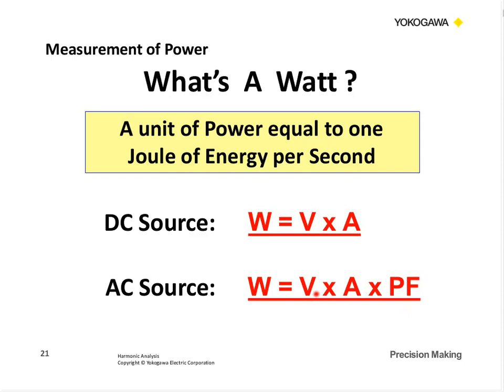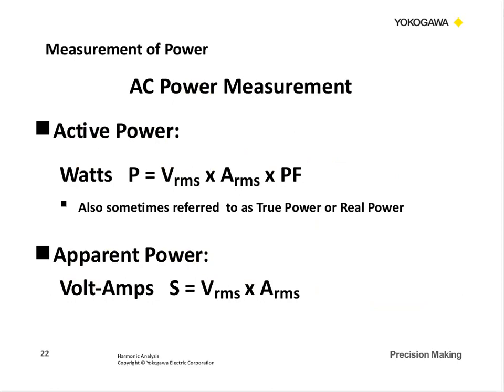Okay, and we don't want to forget that power factor component. So it's not just multiplying voltage and current. That'll give you volt amps, not watts. And I note that I say power factor, not cosine of theta. A lot of our education, you might have heard, well, volts times amps times cosine of theta, or the angle between the voltage and the current. We'll show you why that doesn't work, so that's why we refer to this as power factor. So our active power is typically defined as watts, RMS voltage times the RMS current times the power factor. You may see the terms true power or real power. All of these are kind of the same thing. Then we have apparent power, which is our volt amps. We use the symbol S, that's a universal symbol used worldwide, and that's just the RMS voltage times the RMS current.